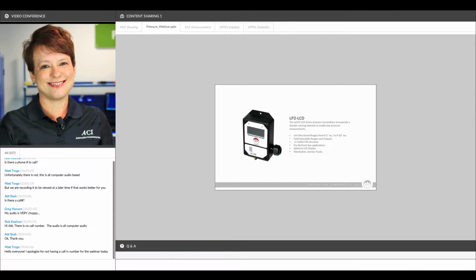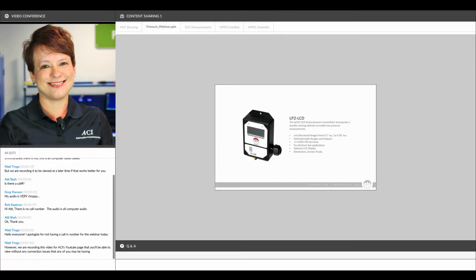There's a few different versions available, each one with 2 to 4 selectable pressure ranges. And because we take this targeted approach to your pressure selectability, you're going to get accuracies on this unit that are as high as plus or minus 0.85% of full-scale output, and that is a guaranteed accuracy no matter what pressure range you're using it on. You can get it with or without an LCD display, and this is a perfect unit for distributors, contractors with service trucks, or anybody that needs a little extra versatility in their pressure transducer because they're just not sure what they're going to run into every day.